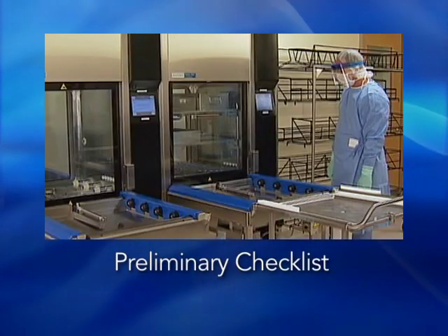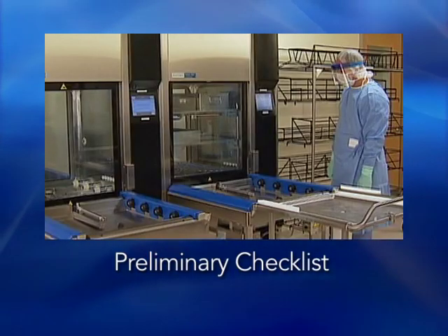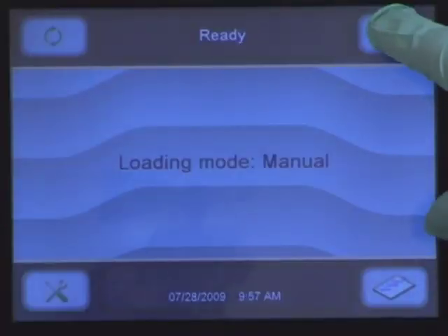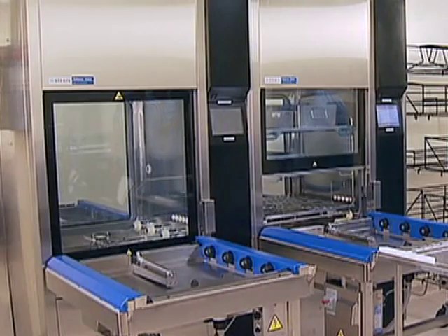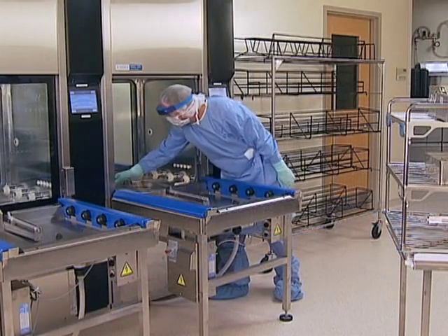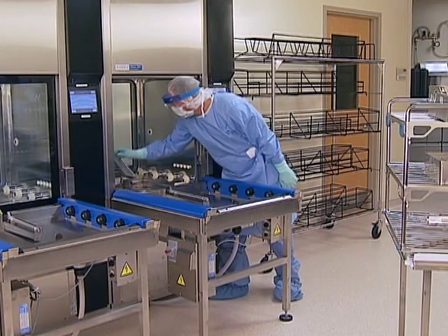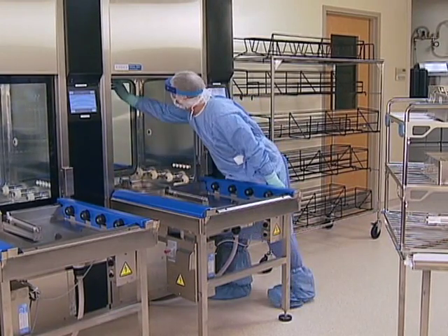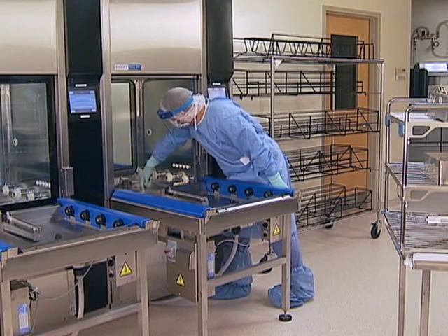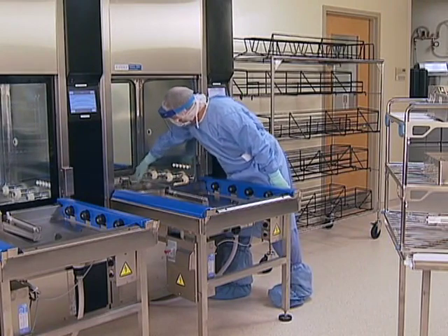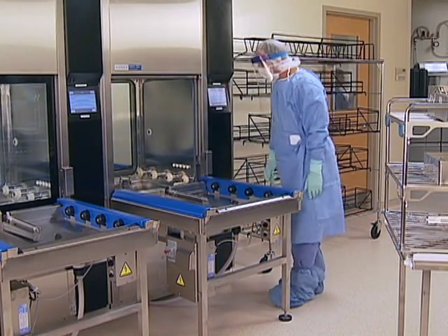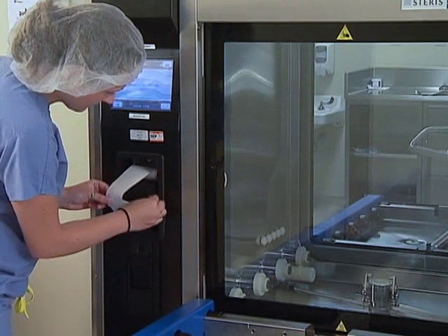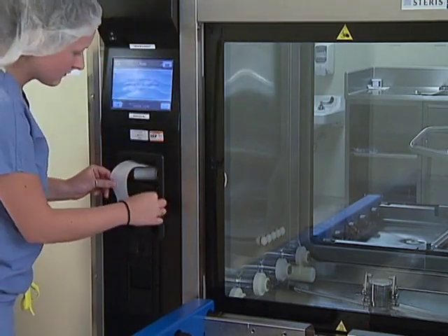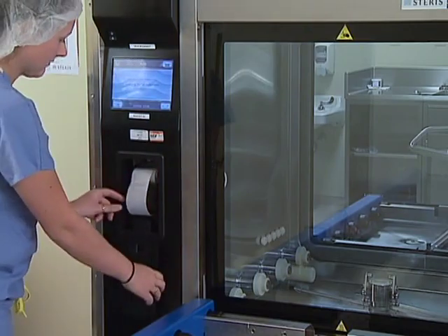Before processing a new load, you'll need to perform a few preliminary steps. First, open the load side chamber door. Make sure the chamber is empty and the debris screen is clean and in place. Inspect the spray arm assemblies to ensure there is no blockage and that movement will not be obstructed during the cycle. Then close the door. On the unload side, the clean side technicians should check to see if there is enough paper in the printer.